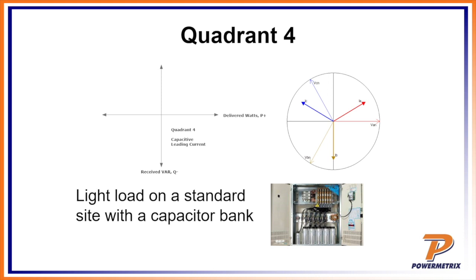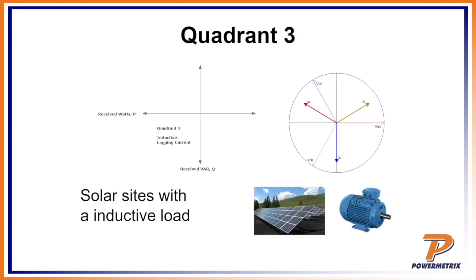That's right. Can you go back one, Chris? Yes. Just to equate to what we've talked about before and relate it to the MeterTech, you'll notice here on A phase that looks like when we have polarity reversal as well. Remember, that does the same thing: it creates a negative power factor, which creates negative watts. Yes, anytime you see that, and we've done it several times on these webinars when we've created a polarity reversal, that A phase looks just like that, and it does the same thing. It creates the negative power factor, and when you have the negative power factor, you get negative watts. That's what we're talking about here.